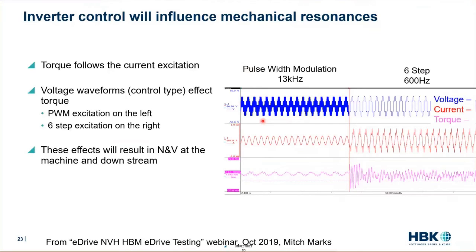This PWM signal is running at 13 kilohertz — turning on and off very quickly — and is being fed into the motor. The motor's inductance filters that high-frequency signal, creating a nice sinusoidal current shown in red — a very clean sine wave with probably some harmonics, but not too bad. Looking at the torque graph in pink below, we can see the torque has a little ripple action, probably caused by some harmonics, but it's not extreme.